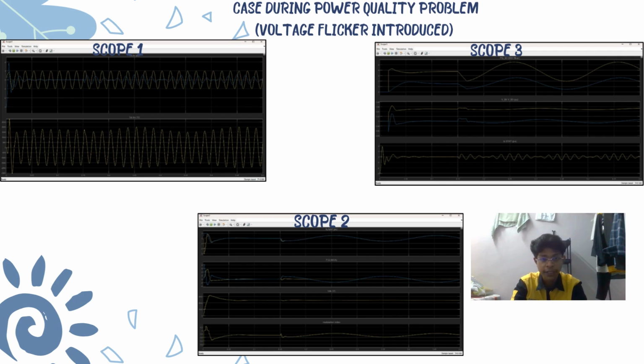So the next result is the case during a power quality problem, which is the voltage flicker introduced in the simulation. In this scenario, the variable load is modulated at 5 Hz to simulate the voltage flicker, while the D-STATCOM is in Q regulation mode with Q ref set to 0. This means it is not actively compensating the reactive power.